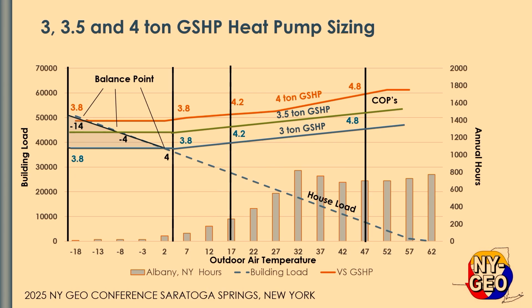So kind of the old sizing would have been maybe more like here, where you have a balance point in the 5 to 10 degree range, and then you would have had a little bit of electric heat that would come on in this area. But I think more normally now is to try and maybe get up here with a 4-ton, where you'd have a balance point that would be way down here, where you're not going to have any auxiliary heat come on at all. So that's probably more normal for what the sizing is going on today, and so that'll result in only the heat pump actually contributing to that peak demand down there.